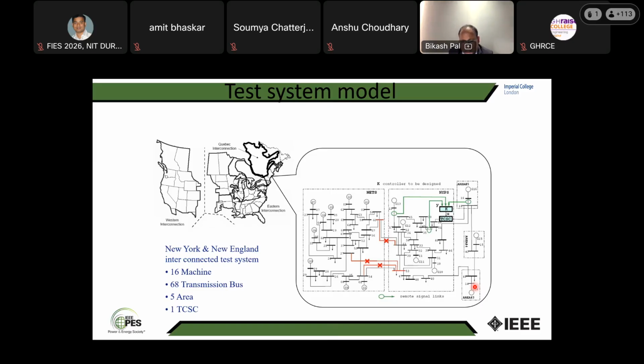We have done the eigenvalue analysis. The one mode is very damped. That has a frequency of 0.79 hertz. All the other modes, like 0.6 hertz, and the other one is 0.5 hertz, and the lowest one is 0.33 hertz, they have very poor damping. And in those modes, certain areas oscillate with other areas. So for any mode, between these 5, there will be 2 coherent areas. In one, there can be 3 areas, and the other can be 2. In one can be 1, and the other can be 4. So that is the mode.